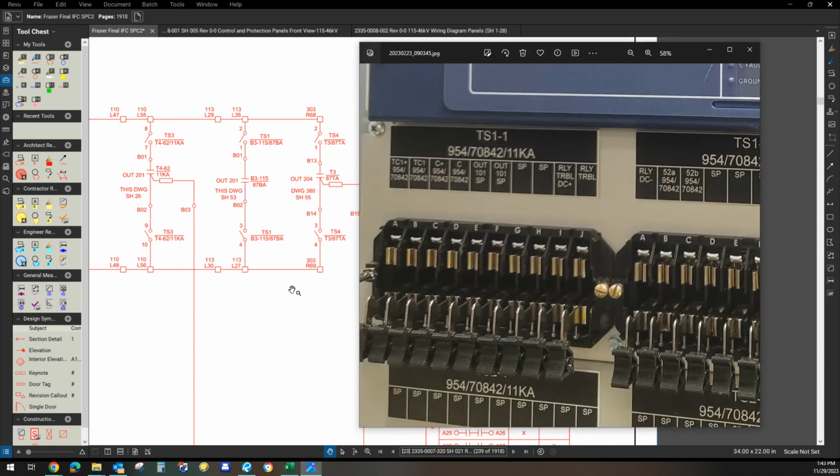So when you look at this, you got to be able to wrap your head around it and understand in your mind that the odd numbers go to the relay, the even numbers go to the field. And you have to understand the flow of electricity as it's going from the positive rail to the negative rail. That's all we did. Okay? We will cover this in detail in another lesson where we're doing isolations. We're going to have a training session on isolations and a training session on restoration. And we'll talk about this in detail again.